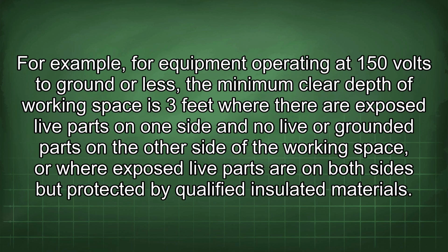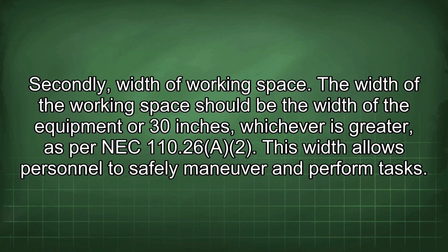For example, for equipment operating at 150 volts to ground or less, the minimum clear depth of working space is 3 feet where there are exposed live parts on one side and no live or grounded parts on the other side of the working space, or where exposed live parts are on both sides but protected by qualified insulated materials. Secondly, width of working space. The width of the working space should be the width of the equipment, or 30 inches, whichever is greater, as per NEC 110.26 A2. This width allows personnel to safely maneuver and perform tasks.